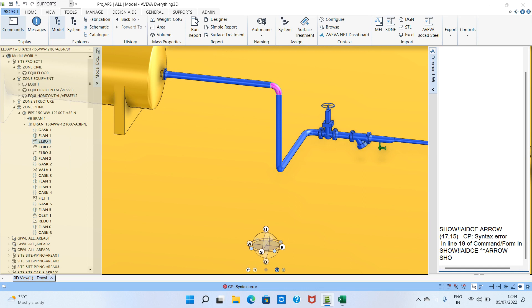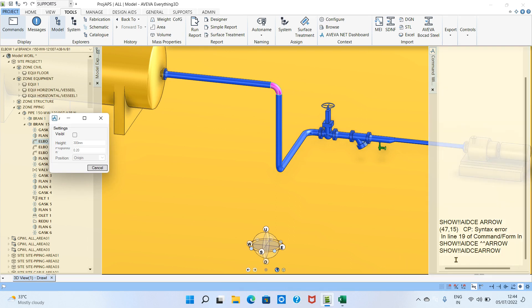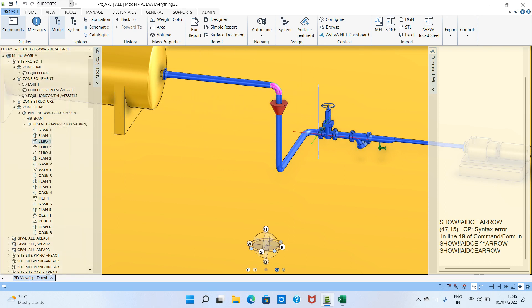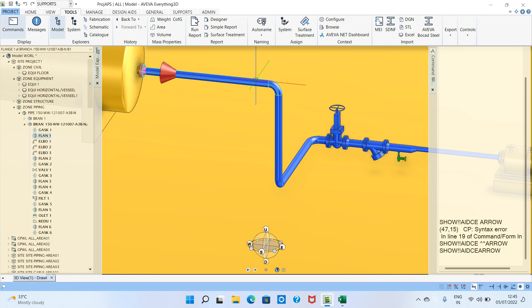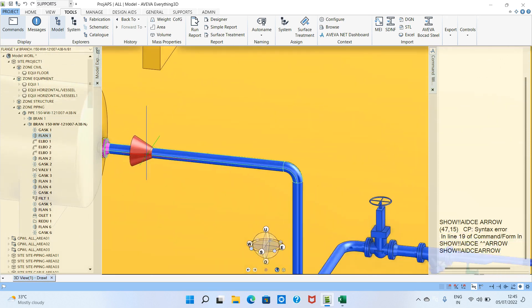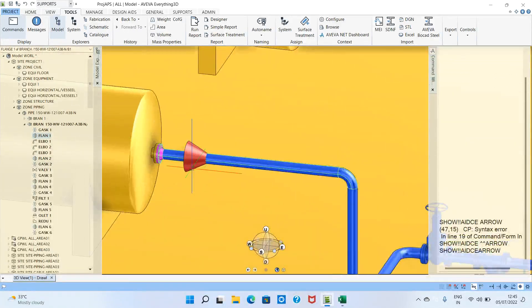Open the tool command and type 'AIDCE ARROW'. This is a PDMS background command. Click here, set visible height to 1000 and proportion to 0.50, then click origin and cancel. You will see the direction arrow showing the flow goes from this point in this direction. Use this command whenever you need to confirm the flow direction of the piping.